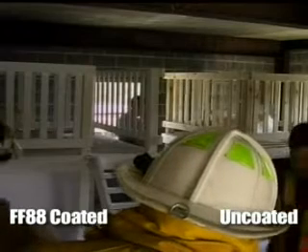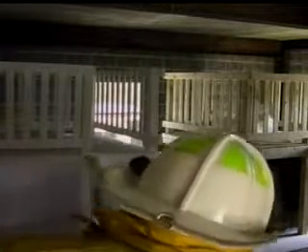The test was conducted on June 21st at the Fire Training Center in Rome, Georgia. You will be viewing two identical loft tests side by side, conducted under the same exact conditions. The room on the left was coated with FF-88 coating, while the room on the right was uncoated. The lofts were made of pine joists, 5/8 inch plywood subfloor, pine railing and 1/2 inch OSB skirts.